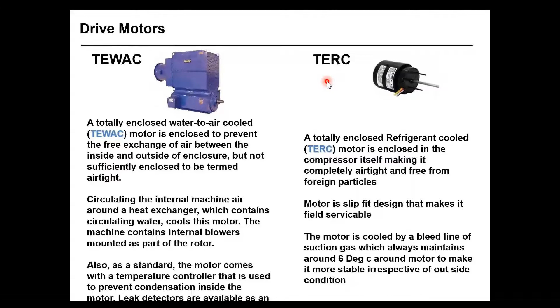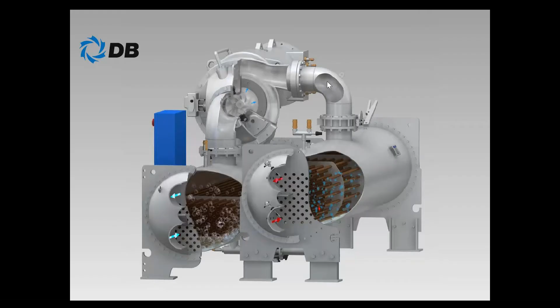We discussed a lot of things. We discussed compressors, impeller, shroud, inlet guide vane, and now you will see all of them play over here. So this is where the evaporation is happening, and this is the suction elbow through which it is getting into the compressor and getting compressed. This is the impeller rotating. You can see there is a rotating part here. The impeller is rotating.